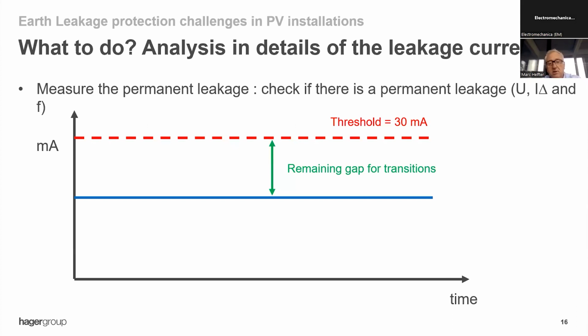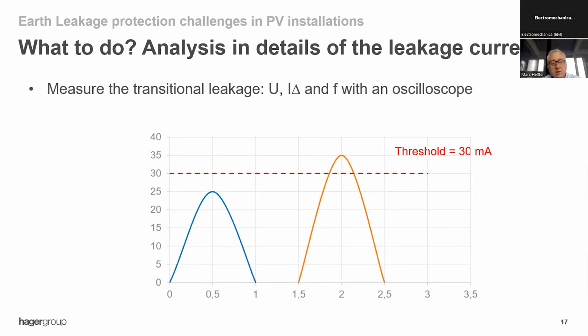Now you can see it on this chart. The threshold is 30 milliamps. If I have permanent leakage, I have only 15 remaining for the transitions. That's one point. And the second point, of course, is to understand what is going on during this transition. What we guess is that there is a kind of peak during this transition. And if this peak is below 30 milliamps, nothing happens, of course. If it's above, the RCCB will trip.